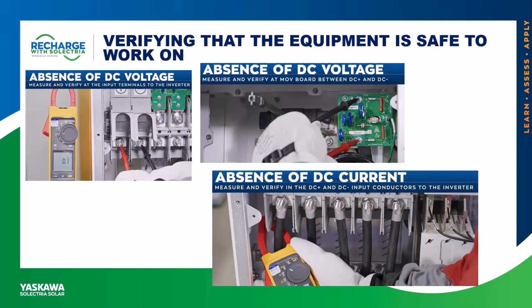So that's why the top picture shows us, okay, we're inside the unit. Let's dig a little deeper and verify there's no voltage potentials still there. Make sure that they're dissipating. It should be anything like 50 volts or less, because by that time it should ultimately go to zero. According to NFPA 70E, it should be 50 volts or less, I believe. That's been updated in recent times, but that was something that was always kind of taught. But again, no voltage is better.